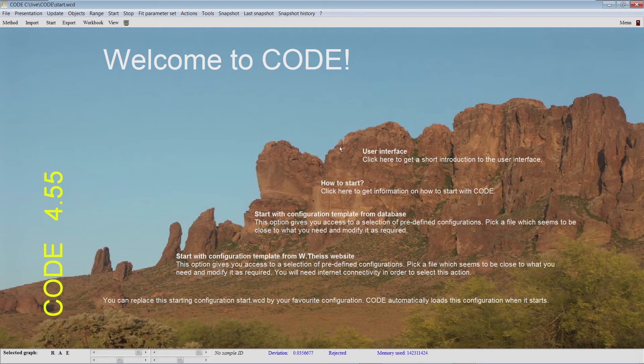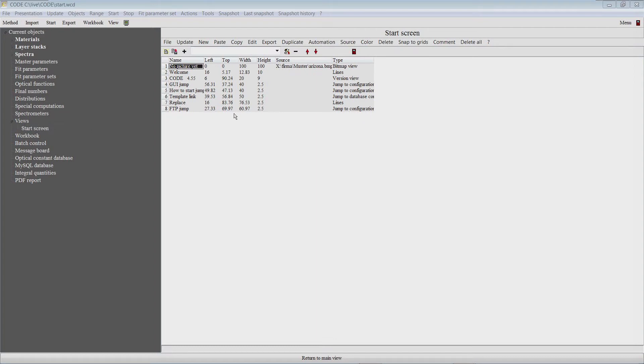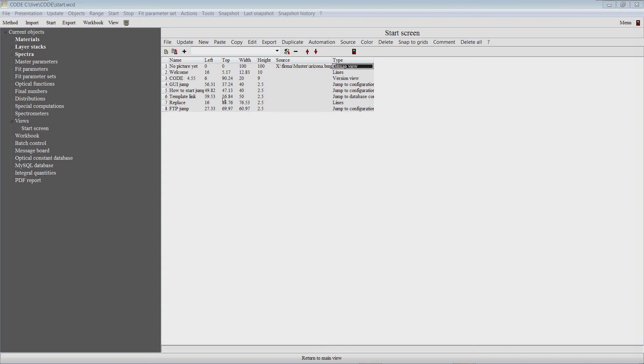The first list I'd like to show you in detail is the list that determines what is drawn on the user interface. The user interface is called main view, and there's a branch here called Views. In Code and Scout you can have several views and easily switch between them. Usually there's only one view defined — in this case it's called 'start screen.' If we want to see the content of this list, we double-click it or right-click it. On the right you see the content of the list, showing various objects. Every object is contained in one line of the list and has a name, some numbers, a property called source, and the object type. A bitmap view will show a bitmap, lines will show several lines of text, and so on.